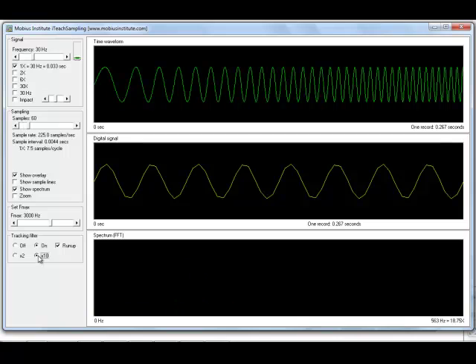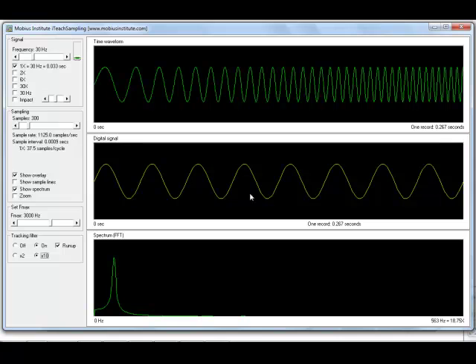If we ramp that up by a factor of 10, we've got a nice analog signal. This is in proportion to the running speed of the machine, so we get a nice sine wave that's always equal to the running speed. Frequency doesn't mean as much anymore — it's just order normalized. This is 1x, whatever the speed is at any time.